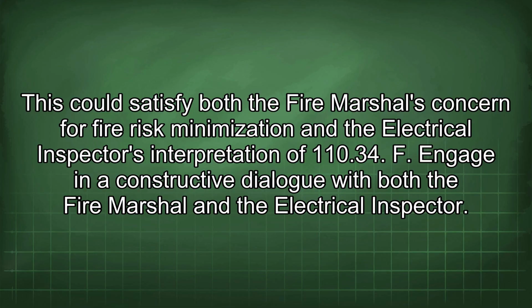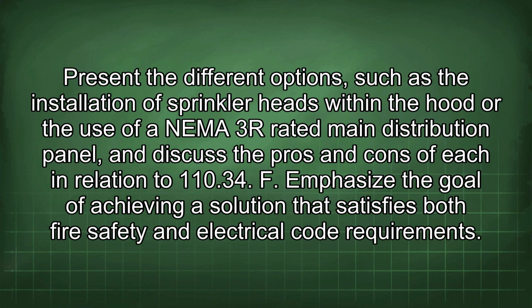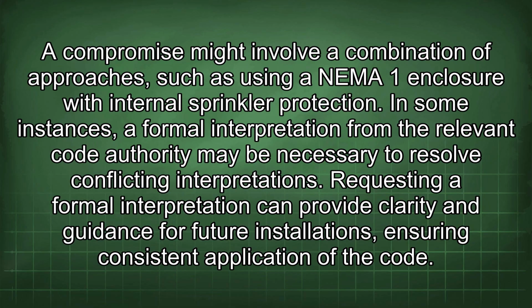Engage in a constructive dialogue with both the fire marshal and the electrical inspector. Present the different options, such as the installation of sprinkler heads within the hood or the use of a NEMA 3R rated main distribution panel, and discuss the pros and cons of each in relation to 110.34.F. Emphasize the goal of achieving a solution that satisfies both fire safety and electrical code requirements. A compromise might involve a combination of approaches, such as using a NEMA 1 enclosure with internal sprinkler protection.